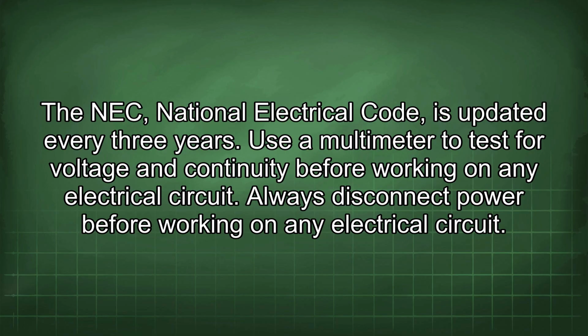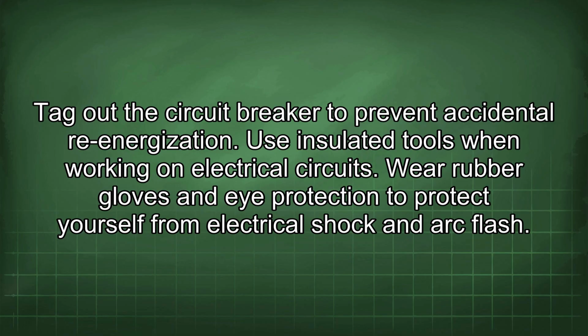Use a multimeter to test for voltage and continuity before working on any electrical circuit. Always disconnect power before working on any electrical circuit. Tag out the circuit breaker to prevent accidental re-energization. Use insulated tools when working on electrical circuits. Wear rubber gloves and eye protection to protect yourself from electrical shock and arc flash.